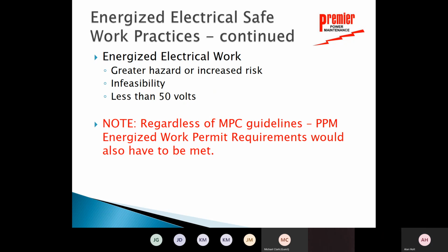Energized work. How about getting an energized work permit? Well, when would you want to do that? Basically, we would just say we don't do energized work. If it can be proven that there's a greater hazard or an increased risk by shutting it down, de-energizing it and going through that whole process, than there is by going ahead and working on it, then there's a potential to get an energized electrical work permit. That's going to be hard pressed to do.